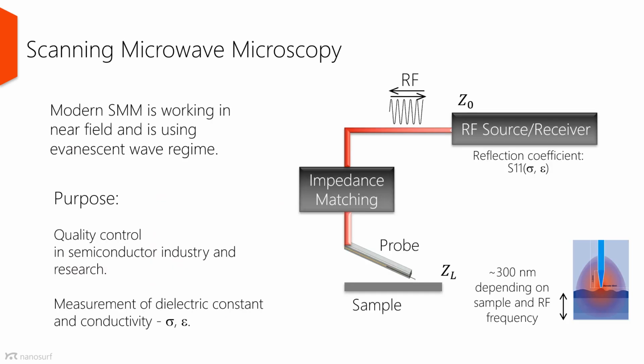The modern SMM is not using free space anymore, because in free space the microwave signal is rapidly losing its power, and I will say a few words about it later. So instead of free space, now we're using transmission lines, which are low-loss coaxial cables. And the reflected microwave signal is collected in the near field or evanescent wave regime. A basic SMM setup would look something like this. You have a microwave source and a receiver, which are usually working on the same port. There are also two port configurations where you can split the forward and the reflected wave, and this could come in handy if you would like to measure the transmission rather than reflection. But the standard configuration is one port.